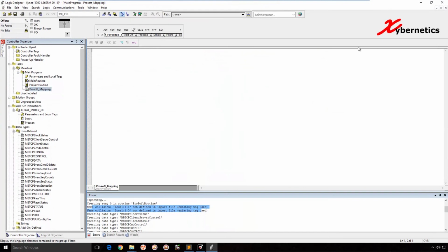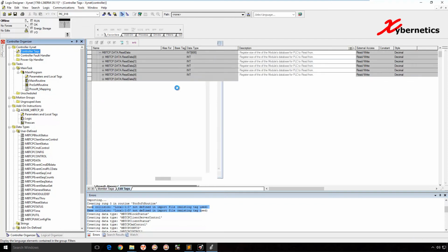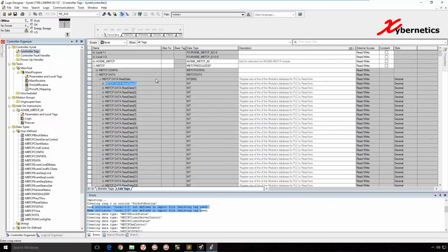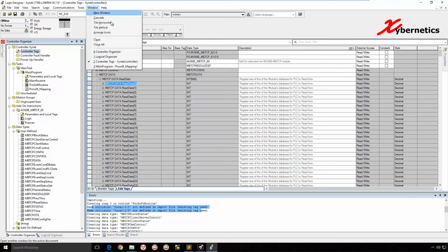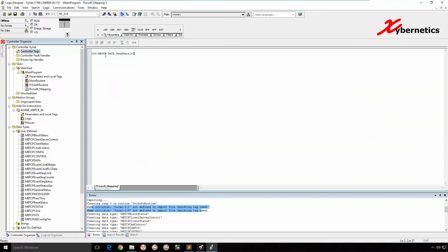Okay, so for example, copy. And then I'm going to go here. So let's say the 40,001, these two are floating point, so I have to read them together. On my structured text, I'll go comma, and then you have to create a tag. I don't know, 1, 2, 3. Say it's a pressure, 2, 4, 6, 8, and call it raw, comma 1. So basically, what this does is hit the Modbus address 40,001.